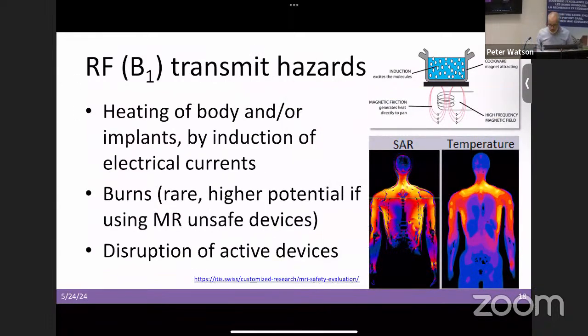The radio frequency, or B1 field, as a potential source of hazard, is mostly on the transmit side, which can produce heating, and that heating can produce burns. Now, most of the time when RF burns happen is because there is another device next to the patient, and there's RF heating of this system, right? The device-patient system that results in electrical currents, and the electrical currents raise the local temperature, possibly resulting in burns. And when they do happen and they get reported, it's usually because an MR unsafe device was used. It's extremely rare that it happens with devices that have been approved for use in the MR environment. The RF field, just like the main field, also possibly results in disruption of active devices. So pacemakers, neurostimulators, drug delivery pumps, etc. They're sensitive electronic devices. You stick them into a magnetic field, they don't like it.